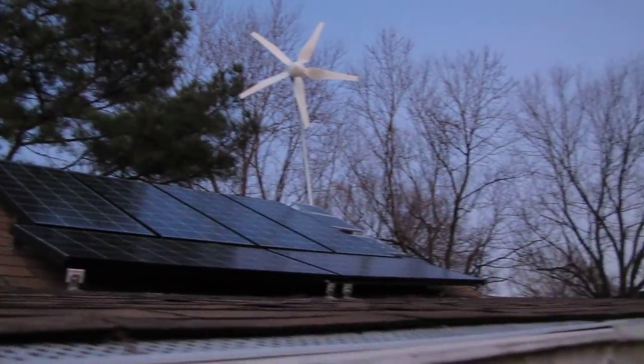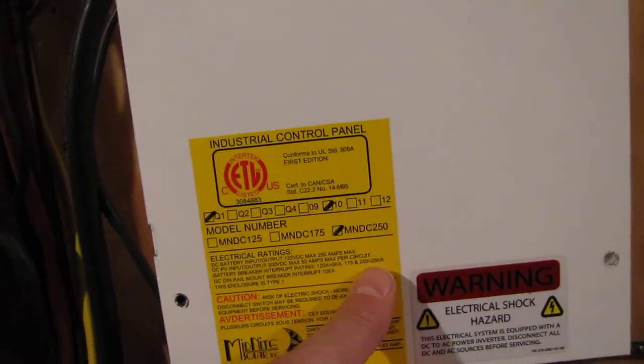This is how every system should be set up. This is my MidNite Solar 250-amp breaker box. I've got my warning stickers on the DC disconnect. I've got everything coming in from my wind going to a 60-amp breaker here. This is my DC PV control, 60 amps, and this is my load control — this turns my charge controller off.